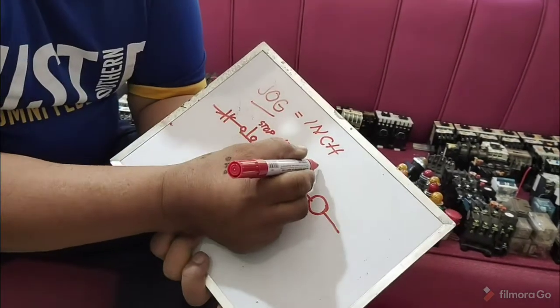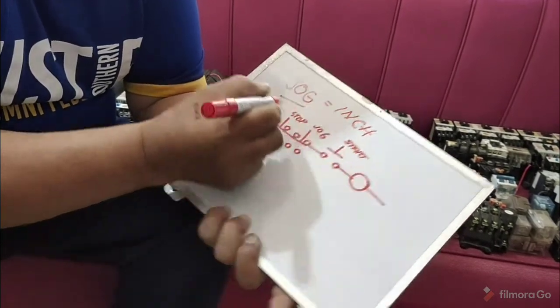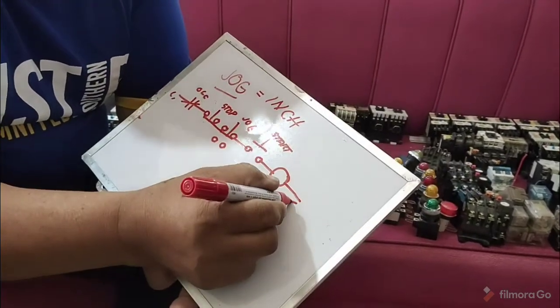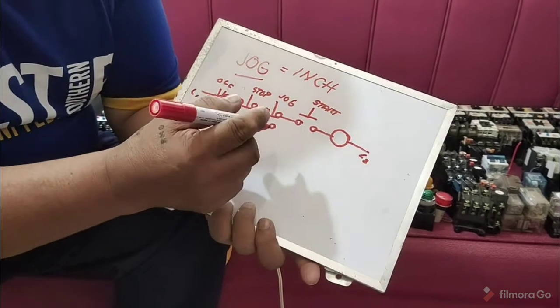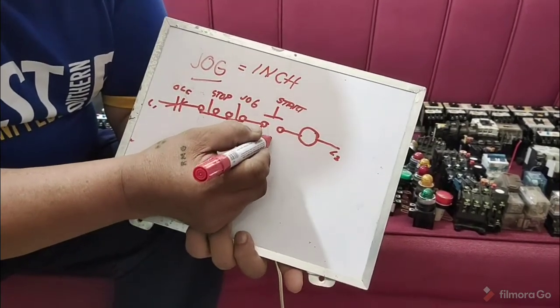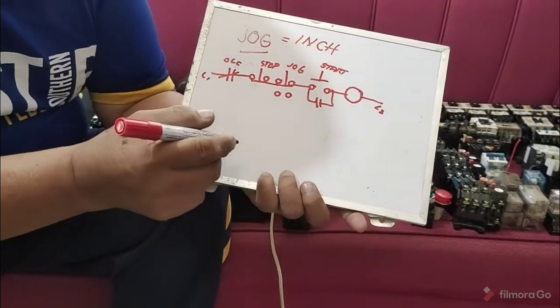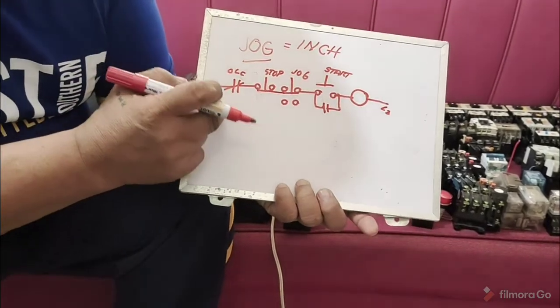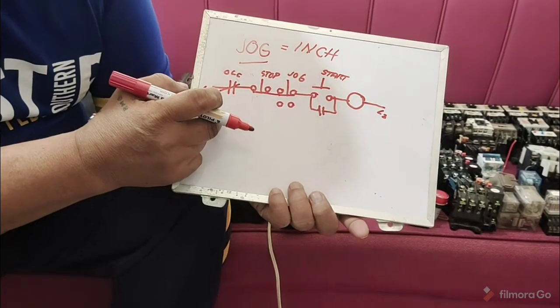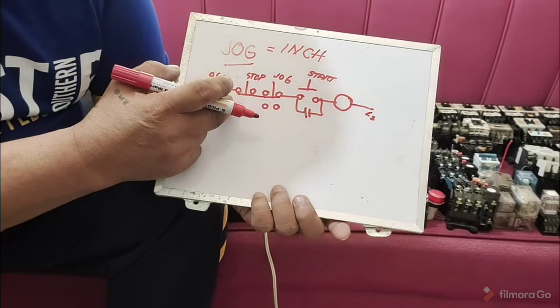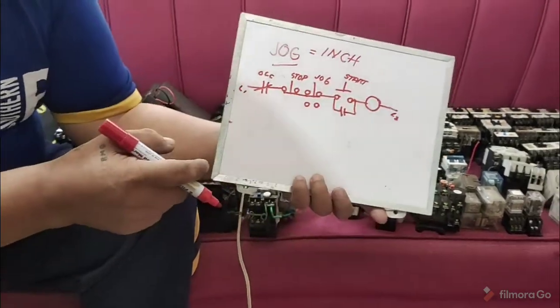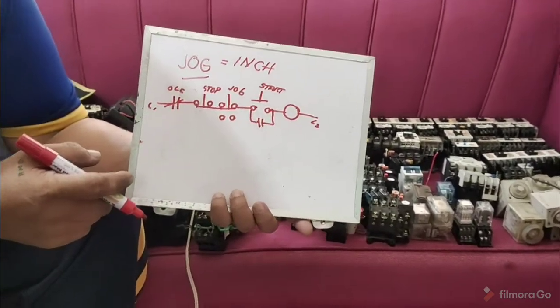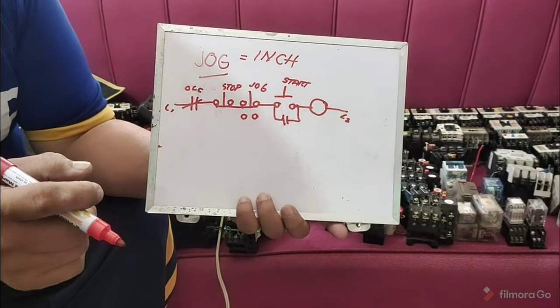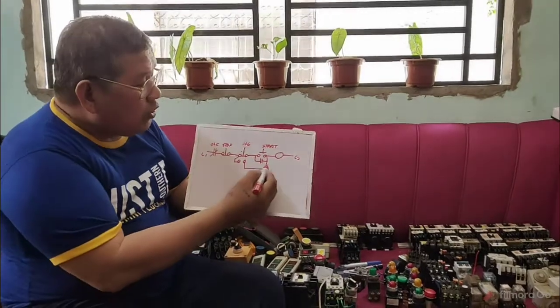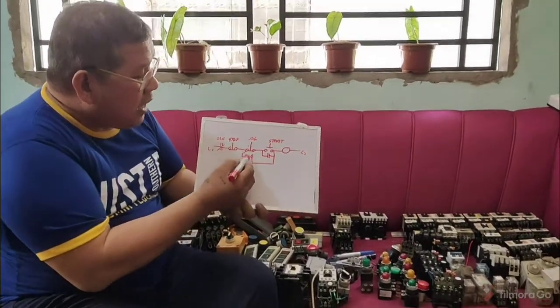So this is your stop button, this is your jog button, and this is your start or on button. Then this is your overload contact, you have your line 1, you have your line 2, that is connected parallel to your power circuit. Then don't ever forget your maintaining contact that serves as the holding circuit. So this is now the control circuit of magnetic across the line or direct online magnetic starter jog operation. Okay, so that is it. Look at that. Make it clear. The same power circuit. Okay, so you have your maintaining contact, and then this is your jog.